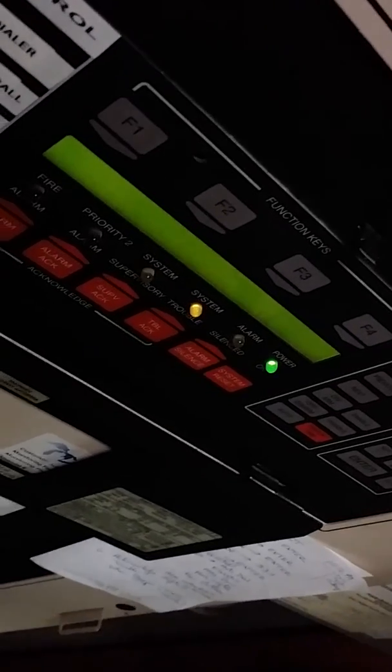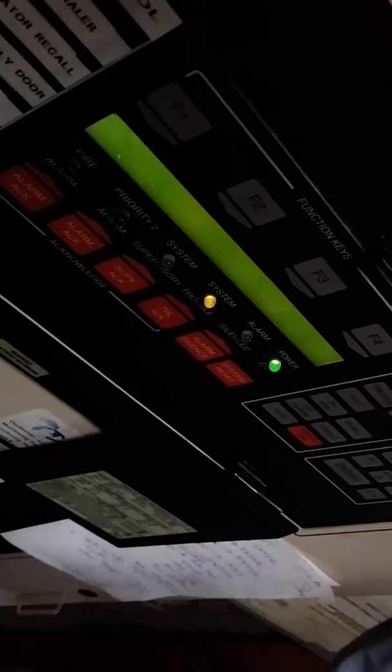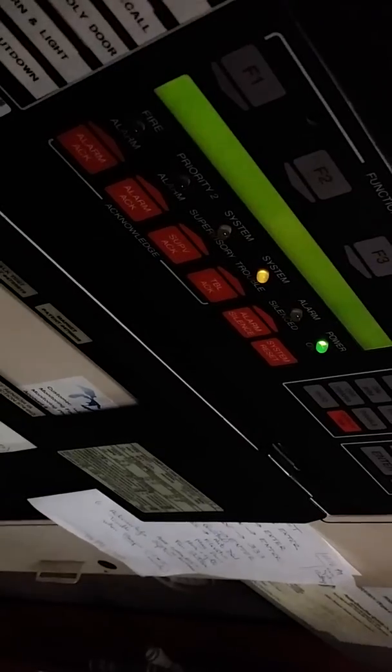Now, if you were in a fire alarm condition, the first thing you would do is you'd come down here and hit alarm acknowledge, you would read whatever it is, and you would report to where you need to verify whether or not it's a false alarm at that point. Sometimes they're good, depends on how they program them in. I haven't seen this one in action to be able to tell you, but the one at the Radisson, I had the same system, was very detailed. It would tell you 6th floor, north end near service elevators. It would actually describe it out to you.